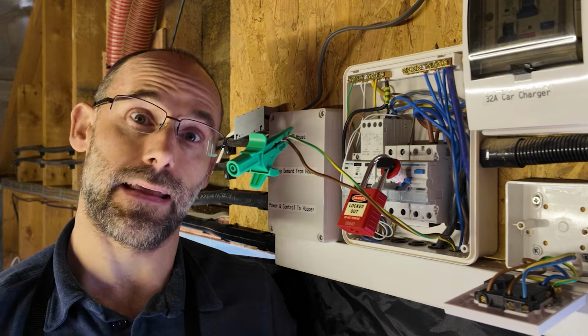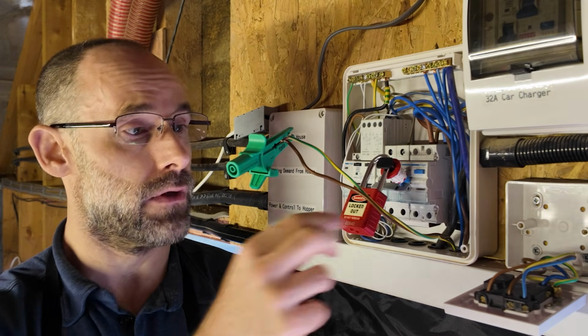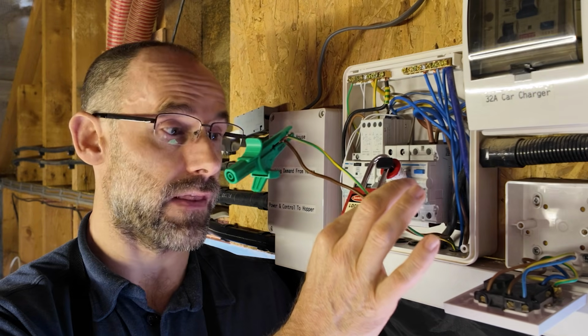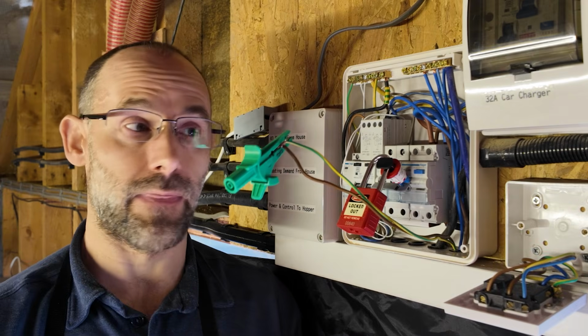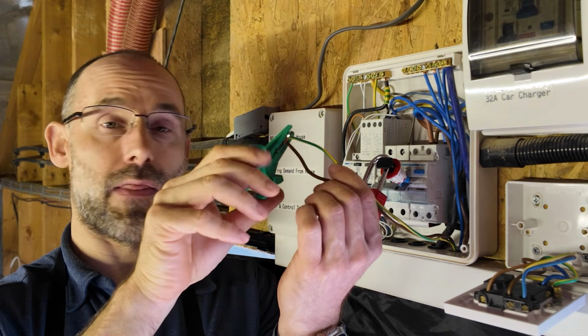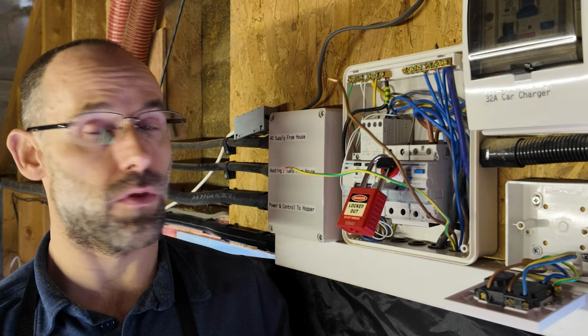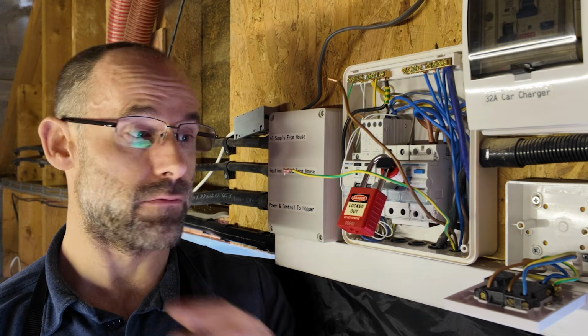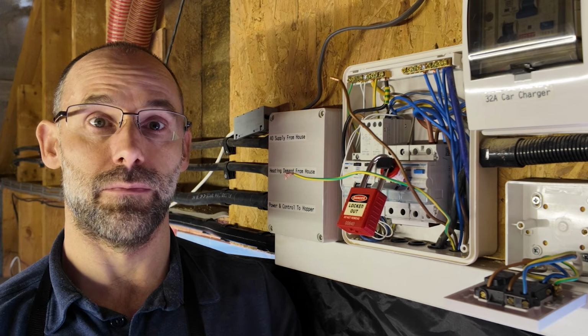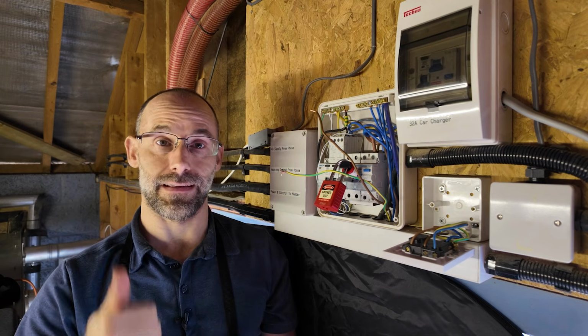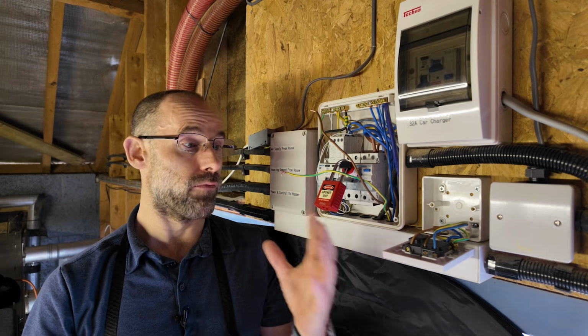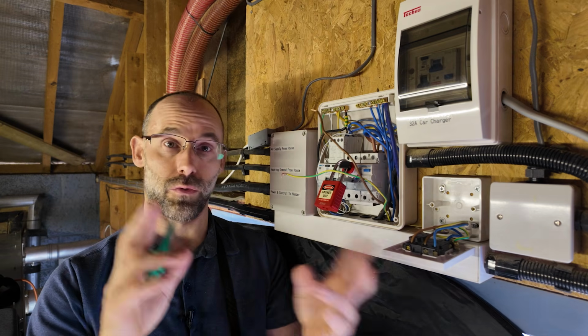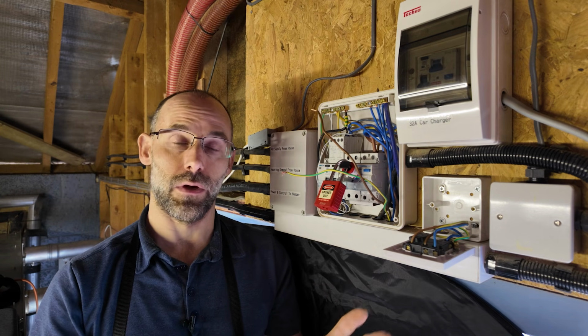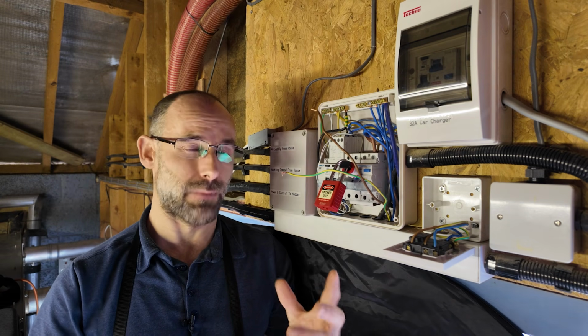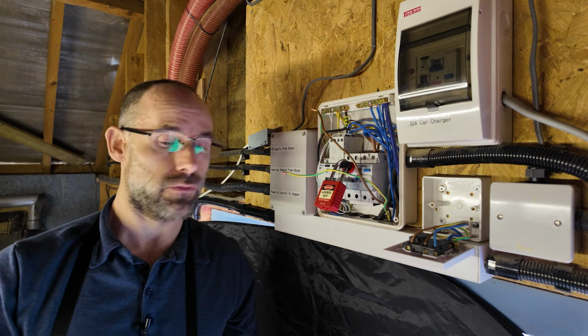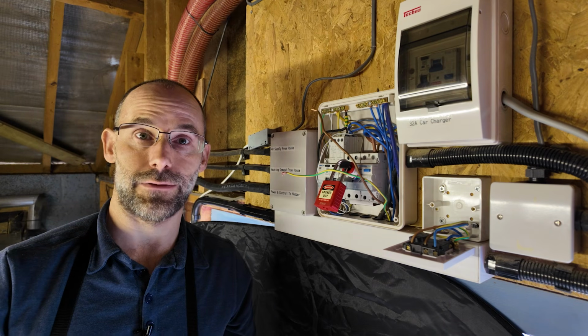Now, you would check that against a table of standard resistance values to make sure that that is a sensible figure for the length of cables. And if you've done that, then you know you've got cables, you know that they're connected, and you know that they are probably operating okay from a resistance point of view because their values match your expectations. So that's it. Step one, it's the continuity of the conductors. And on a simple, what's called a radial circuit like this, that's all we need to do. With ring circuits we have in the UK, it's much more complicated. But for a radial circuit, that's all we need to do at this stage.